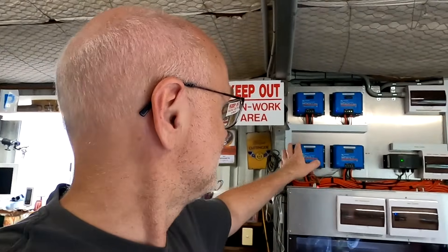It makes sense that the BMS and battery tell the inverter — your charger — what it actually needs. As you know, I have my battery shelf set up without any communication to the Victron system, so neither the MPPT solar charge controllers nor the inverters know anything about the batteries apart from voltage and current the smart shunt measures. The MPPTs don't know when to slow down when the battery gets too hot, current too high, voltage too low, or when one cell is peaking.